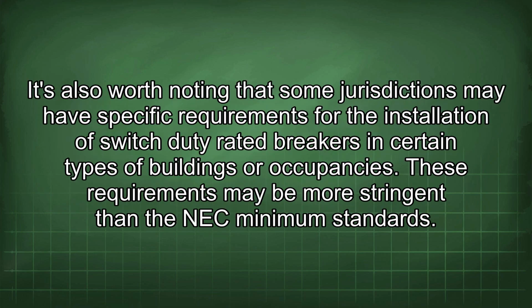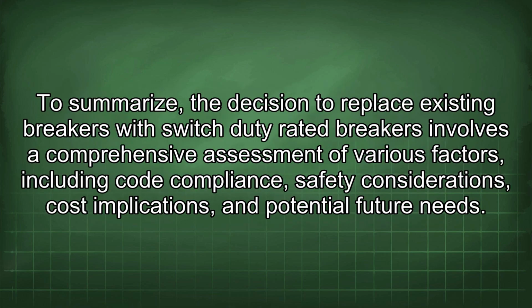It's also worth noting that some jurisdictions may have specific requirements for the installation of switch-duty rated breakers in certain types of buildings or occupancies. These requirements may be more stringent than the NEC minimum standards. To summarize, the decision to replace existing breakers with switch-duty rated breakers involves a comprehensive assessment of various factors, including code compliance, safety considerations, cost implications, and potential future needs.